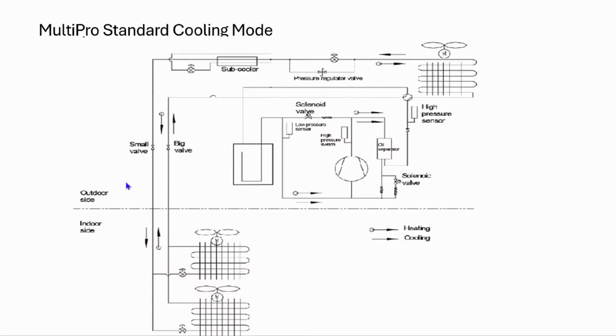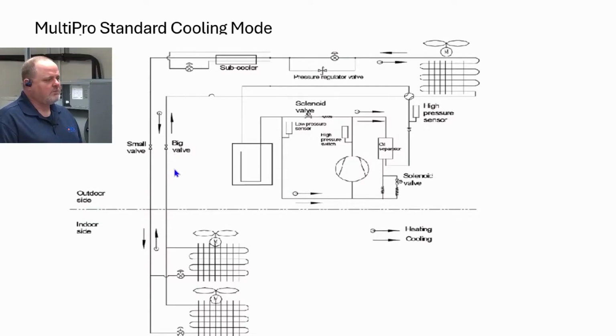So as you can see right here, these would be your service valves on the outdoor unit, your small valve and big valve. They call them the small valve and big valve because they're not really, the way we've always done unitary product or traditional heat pumps, stuff like that, that we've always called them liquid and suction line, right? Right, yep. So on these, though, it depends. If you're in heating mode, the big line is going to be your discharge. Your small line is still going to be your liquid. And then in cooling mode, your small line is still going to be your liquid. Now, the large pipe becomes the gas pipe.